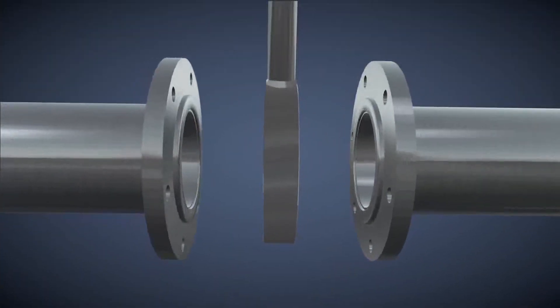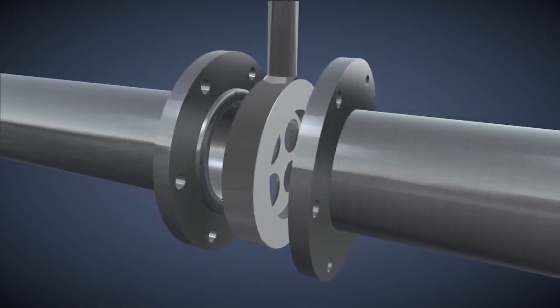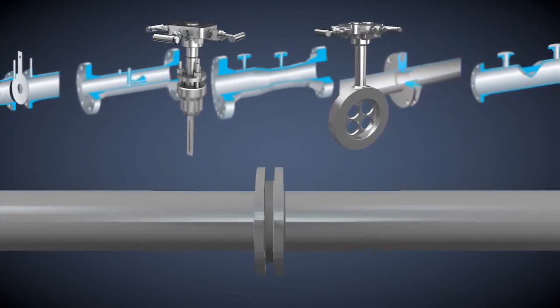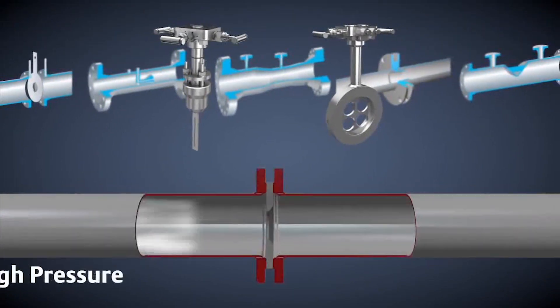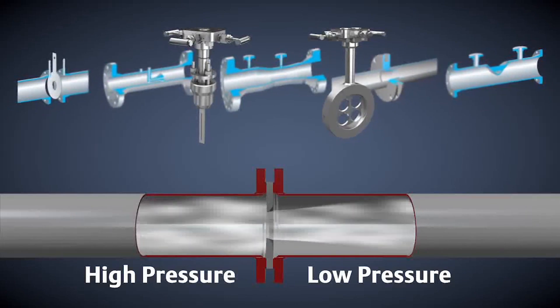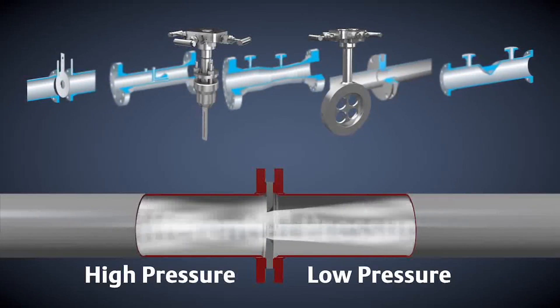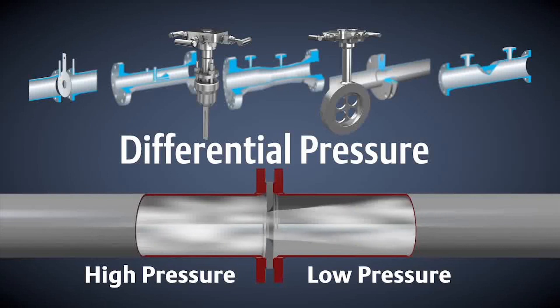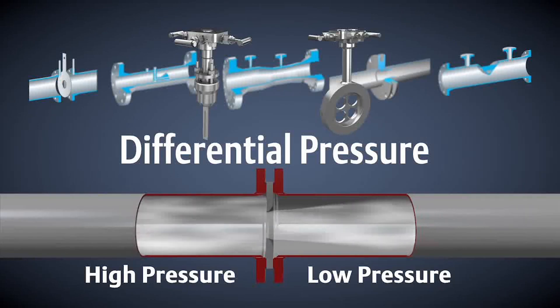Primary element selection is dependent on process conditions. All of these different primary elements have one thing in common: they constrict the flow in a pipe, causing a pressure drop from one side to the other. The difference in pressures is the differential pressure, and the square root of DP is proportional to the flow rate.